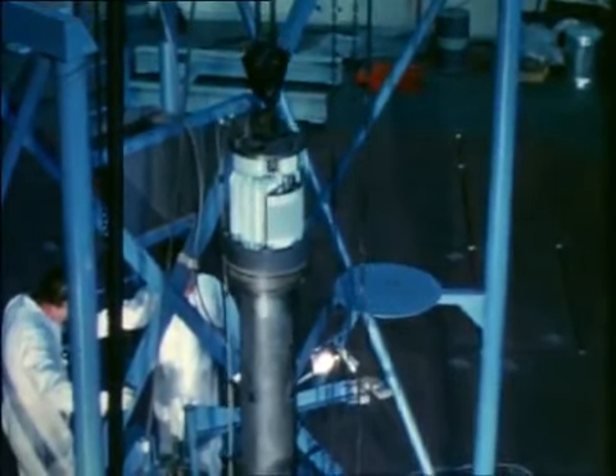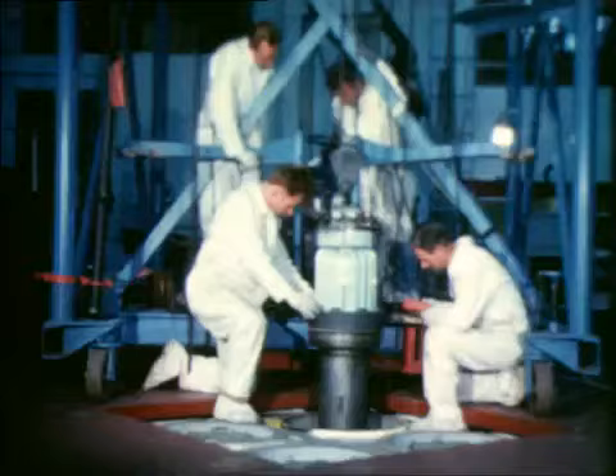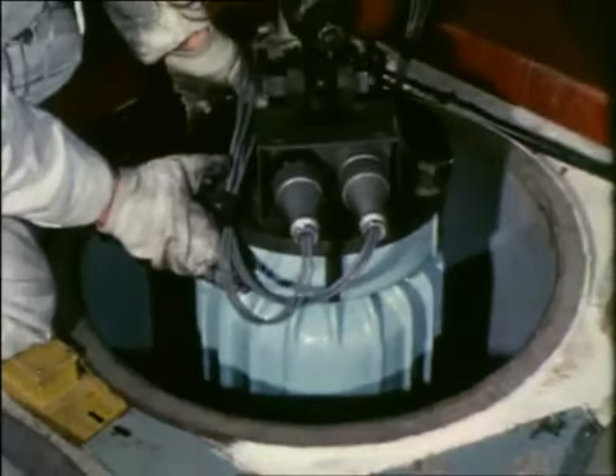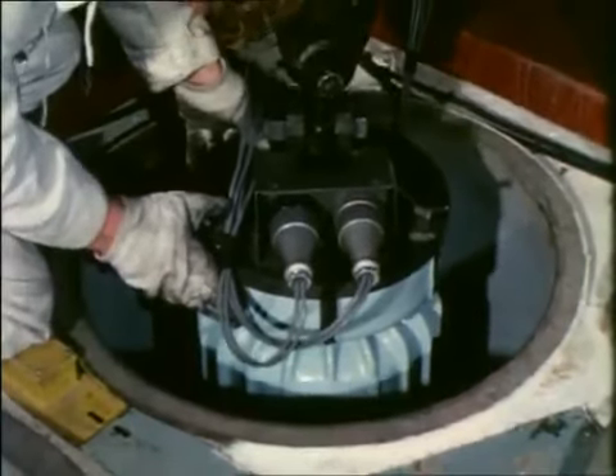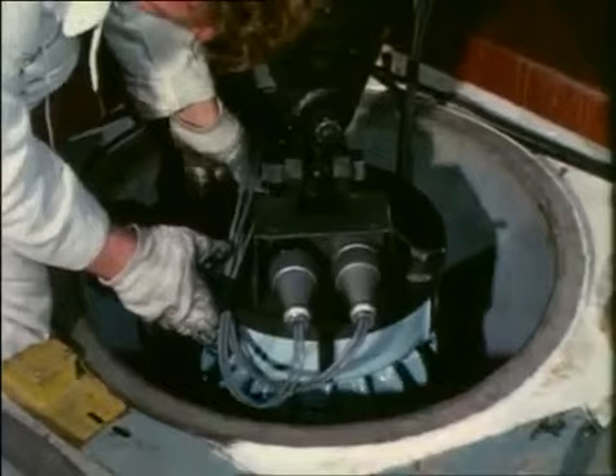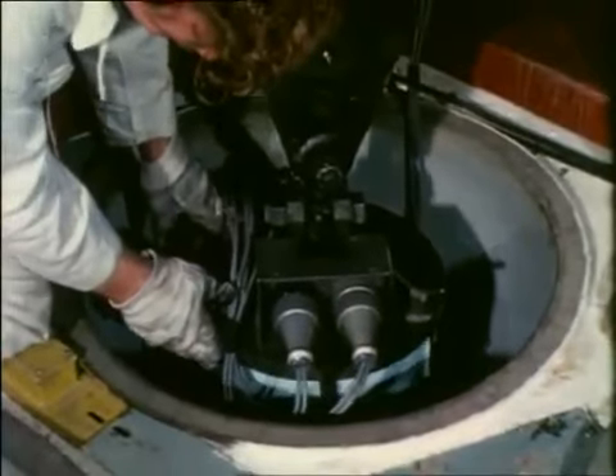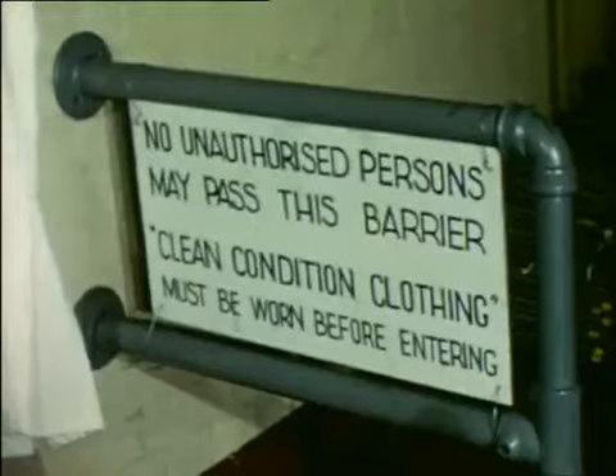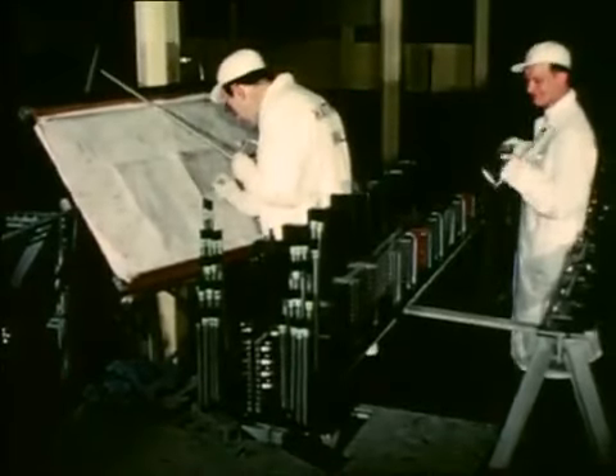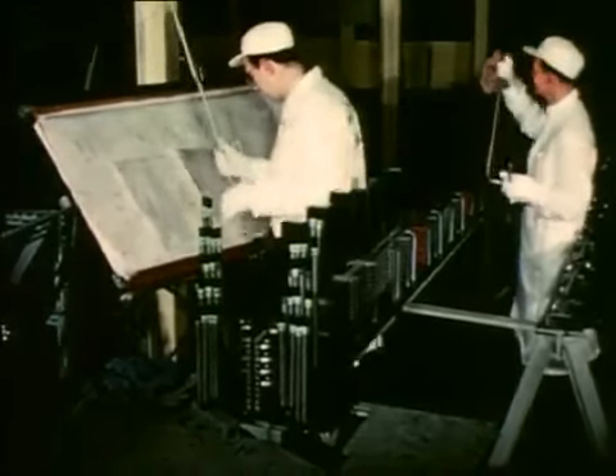One or two of the fuel elements, there are over 42,000 in each reactor, one or two may fail in use, and special equipment had to be designed to detect and locate the suspect or burst cartridges in time to remove them before any significant contamination developed in the coolant circuit. This is the equipment being prepared in a London factory for dispatch to Berkeley.